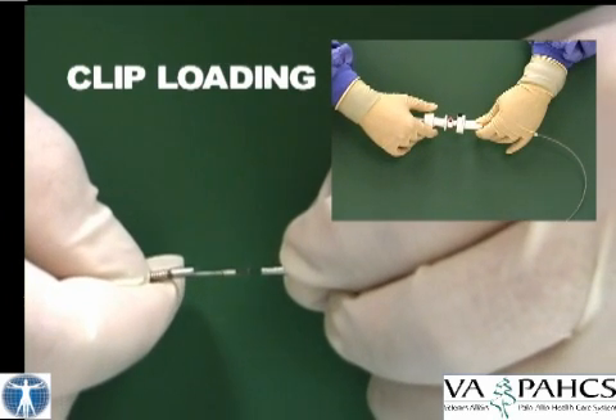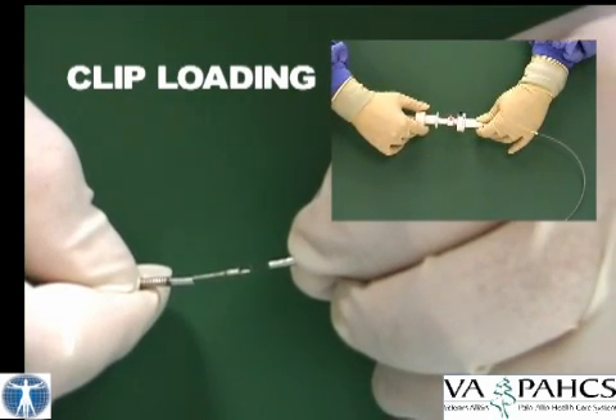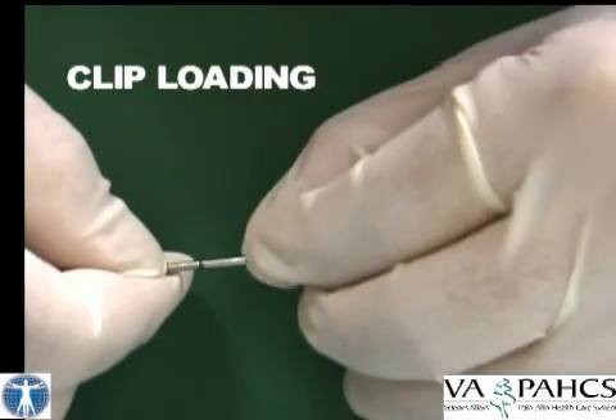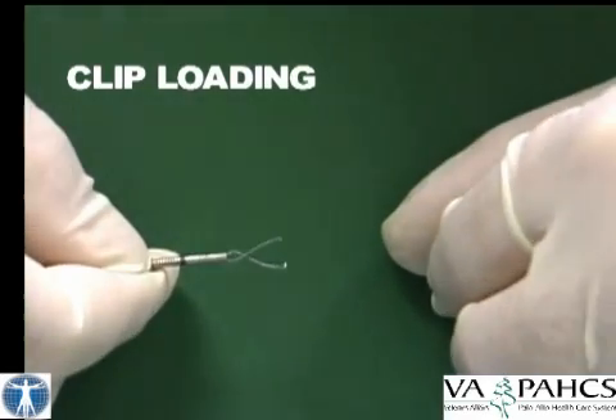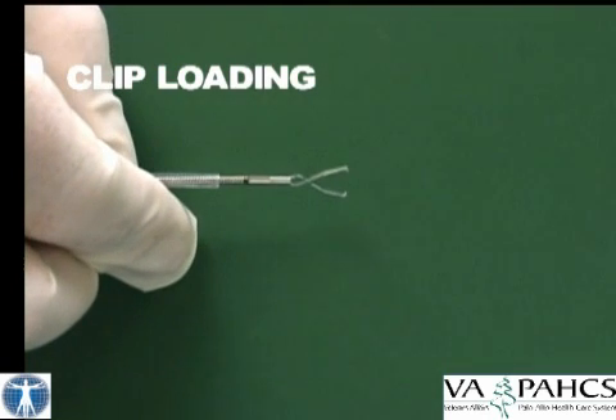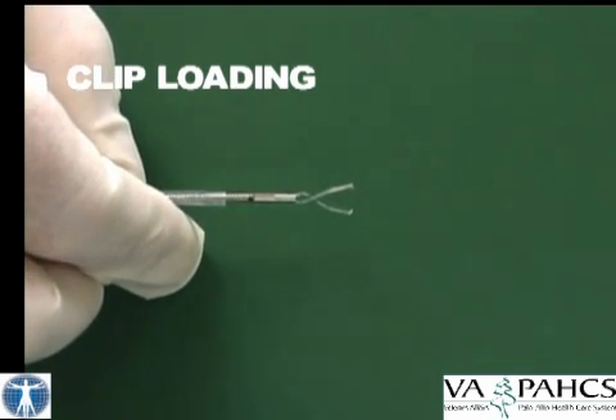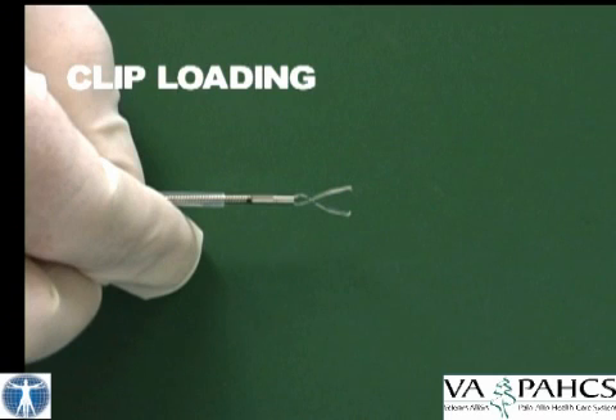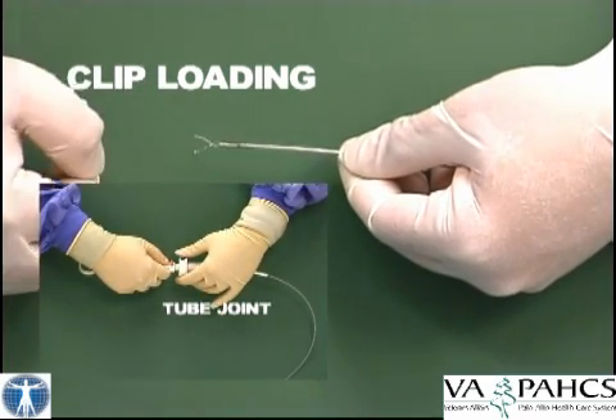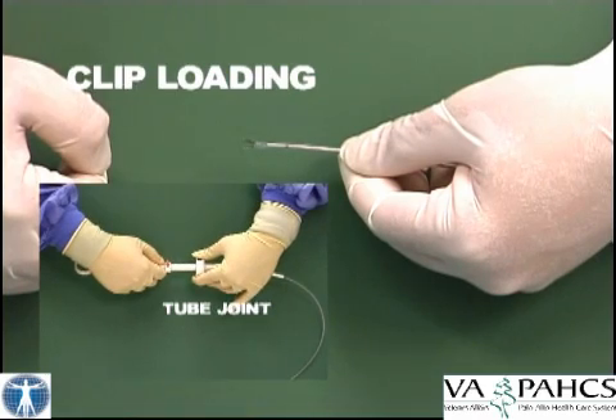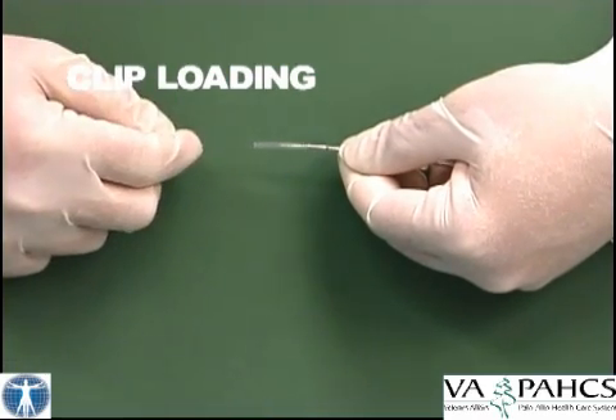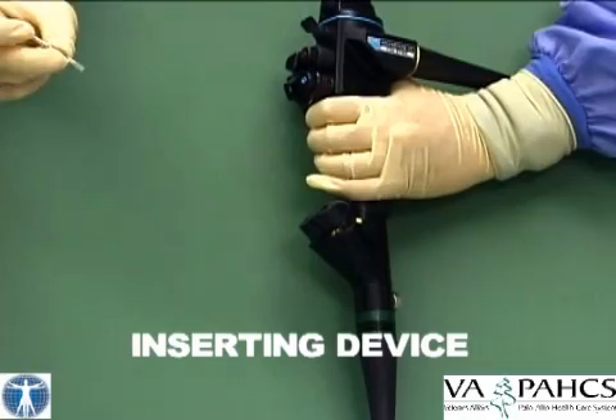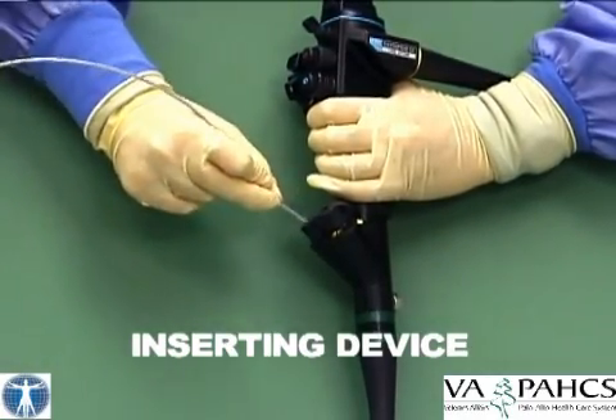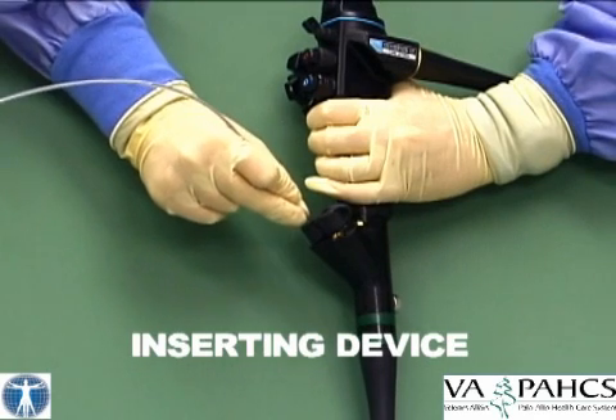The operation wire is retracted into the coil sheath by pressing the green ratchet release button and partially withdrawing the slider until the clip pipe fits into the end of the coil sheath. Note that further retraction of the slider will prematurely retract the spring loop and widen the clip prongs. This should be avoided. To pull the clip into the tube sheath, advance the tube joint away from the handle ring. This will close the clip prongs. Hold the apparatus near the tip to avoid bending the clip while inserting into the working channel of the endoscope.